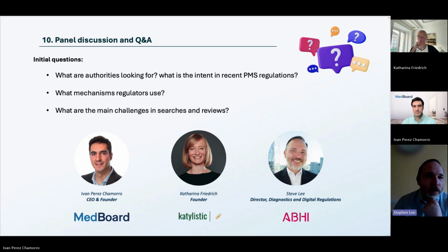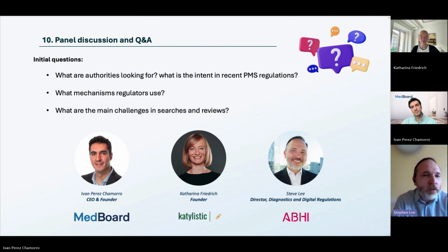I would say in addition, you've got things like proficiency testing and EQA, which you should be adding into your knowledge about the performance of the device, because they will give you a comparative performance compared to other similar products in the field, and that can be an invaluable source of information about performance in the post-market phase.